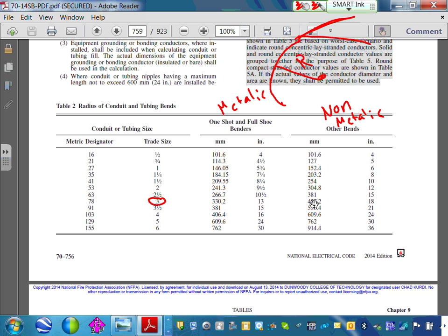Okay, EMT, Brandon, what's EMT, is it metallic or non-metallic? Metallic, I hope you got that. Okay, what's the bending radius for 3-inch EMT, is it 13 or 10? I can see, 13 inches bending radius. Now what happens, 3-inch PVC, if it was PVC, what would be the minimum bending radius? Is it 18? 18, can you guys see that? So when you're a project manager and you're going around and you see a conduit that's bent so sharp it almost broke, that means the bending radius is not followed.